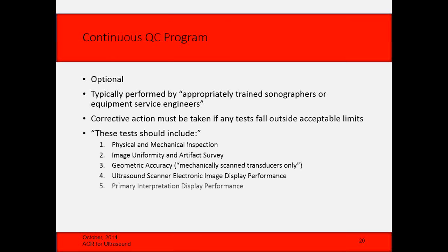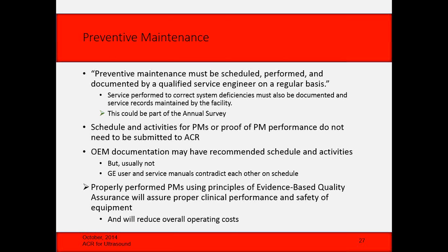So what I say is that if you perform PMs properly using the principles of evidence-based quality assurance, you will assure that the system is performing properly to provide a diagnosis, and you'll also make sure that it's safe to use, so you're not going to hurt somebody with it. And actually it's been proven you will reduce your overall operating costs, because if you do these on a regular basis, you'll find problems when they can be fixed for a little less money than it might cost. So for instance, a good example is a transducer with the membrane starting to delaminate. You see a little bit of dropout. If you don't catch that in time, the membrane separates far enough, and then stuff starts getting underneath the membrane into the array, and eventually it will destroy the array. So you've gone from one of the most inexpensive repairs of a probe to having to replace the probe.